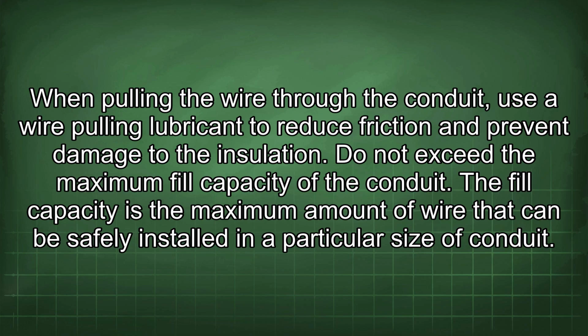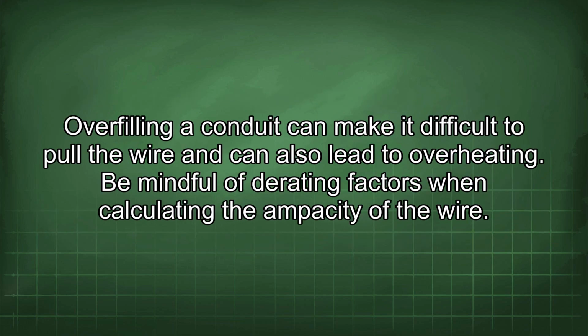When pulling the wire through the conduit, use a wire pulling lubricant to reduce friction and prevent damage to the insulation. Do not exceed the maximum fill capacity of the conduit. Fill capacity is the maximum amount of wire that can be safely installed in a particular size of conduit. Overfilling a conduit can make it difficult to pull the wire and can also lead to overheating.